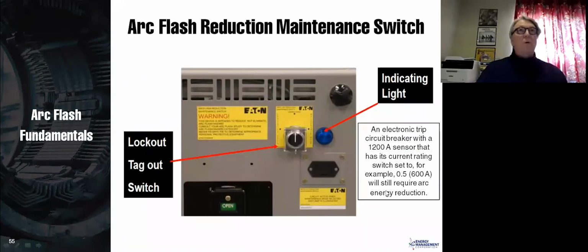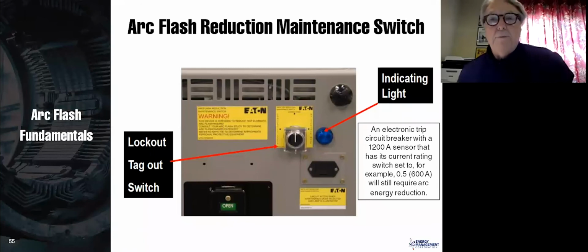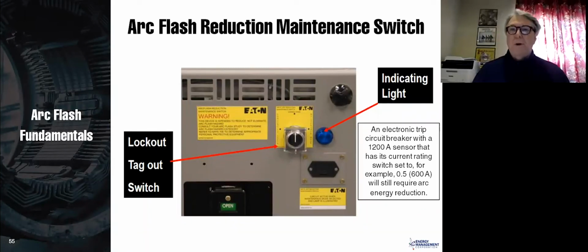I've got a breaker. I want to use a short time delay because I want to maximize my breaker coordination. So I get a breaker with an arc flash reduction maintenance switch. These things are becoming very, very popular these days. When I put this in normal mode, then I have my short time delay. When I put it in maintenance mode, it eliminates the short time delay and gives me an instantaneous trip. Therefore, I'm going to put it in normal mode when I'm not working on equipment. When I work on the equipment hot, I'm going to put it in maintenance mode. It eliminates the short time delay, and my calories may come down from 30 to 1 or what have you.